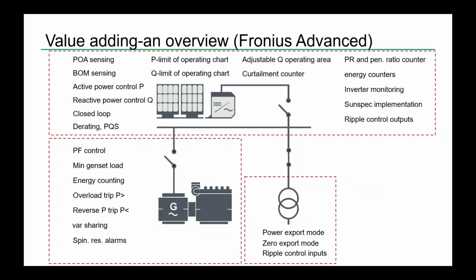I have made this slide. It shows a little overview so you can see what you actually get with the different solutions. So the Fronius advanced solution will of course give you inverter control. We can see in the upper box you have the active power control, reactive power control, and this is of course the most important. Closed loop functionality is available, meaning that the system compensates itself if you have a dropout of an inverter or something fails. Then we have other factors like counters and the possibility for monitoring your sensor inputs. These are key elements for the inverter.